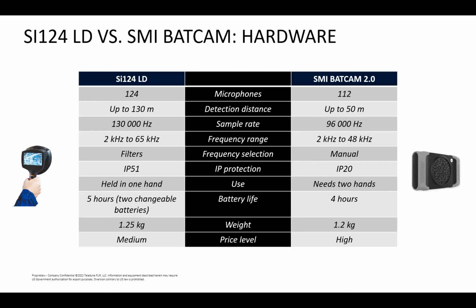Despite this, the camera finds all the leaks you need to find. With the exception of some very tiny leaks that aren't common, for example in compressor detection, the camera is able to find really tiny leaks, and our sensitivity thresholds are the best in the market for acoustic detection.